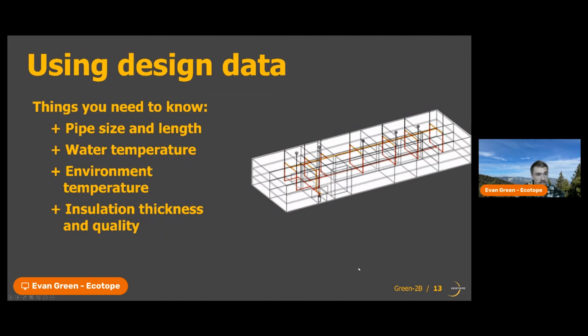So we'll also need that temperature differential that's driving that heat loss. That's going to be the difference between the temperature inside the pipe, being the water temperature, and the temperature of the environment that the pipe's in, whether it's in a parking garage, or outside the building for some reason, or in conditioned space. We'll also need to know the insulation thickness and quality, which is usually pretty easy to gather because it's going to be code required in the jurisdiction that you're designing around. So you should know the insulation thickness and the conductivity of that insulation.